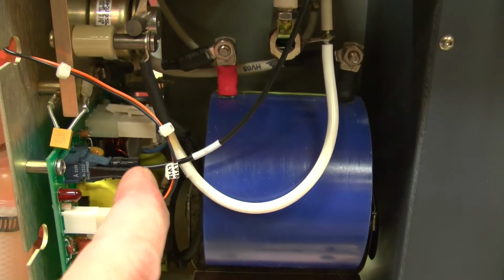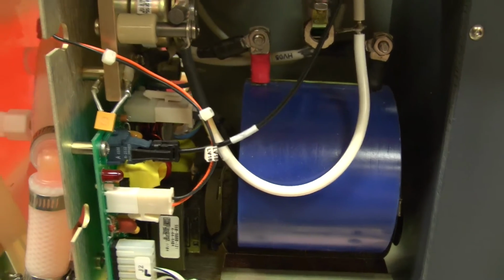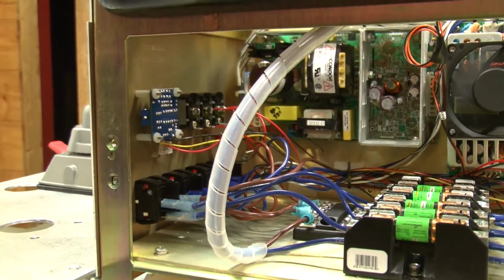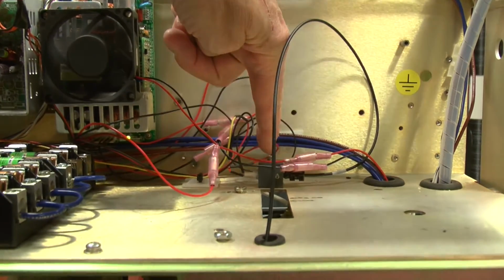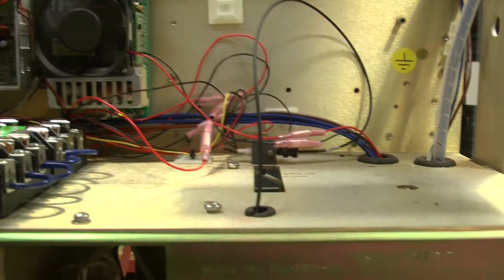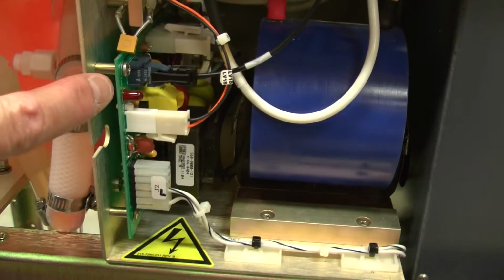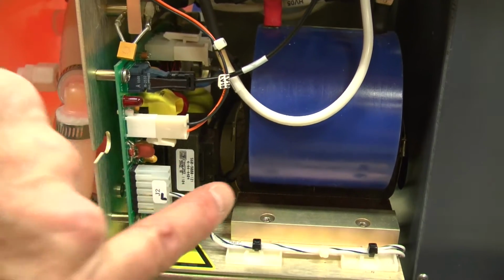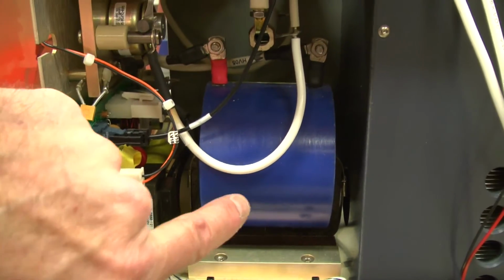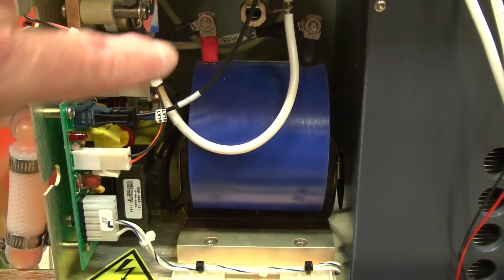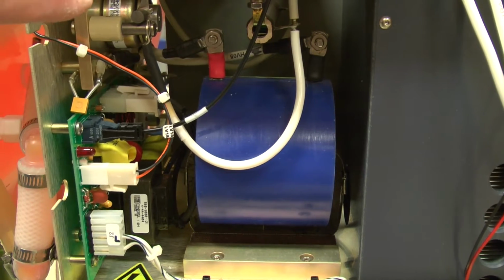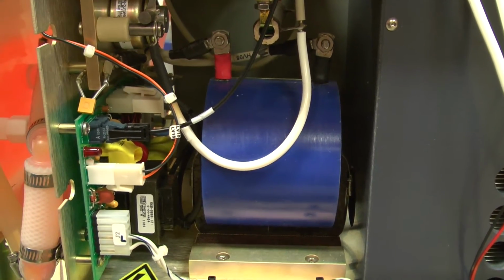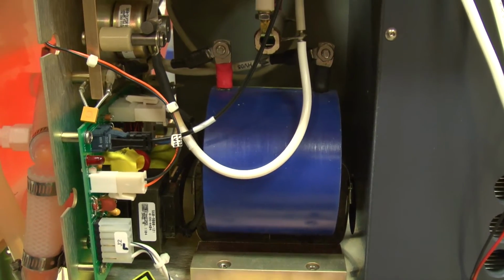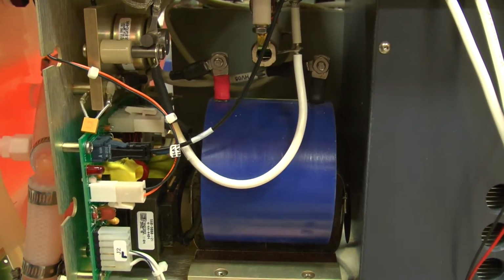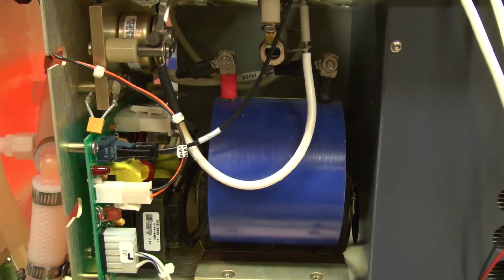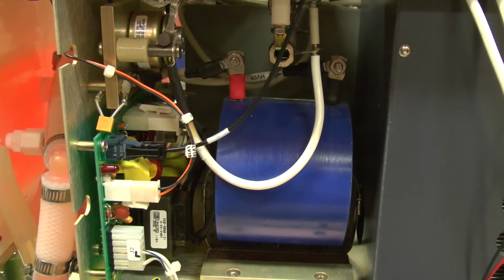What then happens is, when a small pulser that's located up here generates a low voltage pulse, it sends the electrical signal to an LED, which through an opto-isolator to here on the board, triggers a 240 volt pulse from a small capacitor into the primary winding of the trigger transformer. This then steps up 100 times to 25,000 volts and is added to the potential across the flash lamp to now 28,000 volts, which is enough to cause the flash lamp to begin discharging. And then the rest of the current can flow from the capacitor. It only requires about 700 volts at that point to then discharge the capacitors.